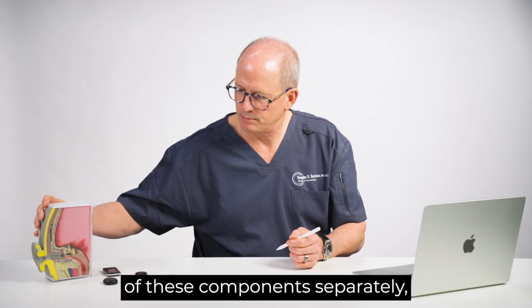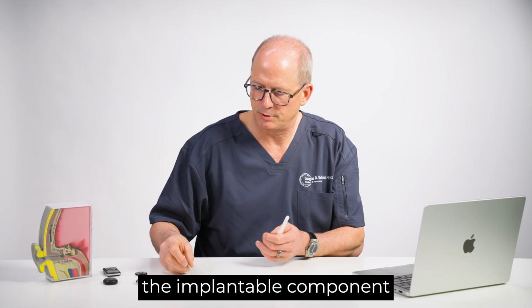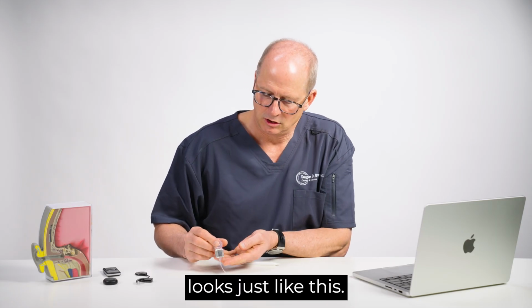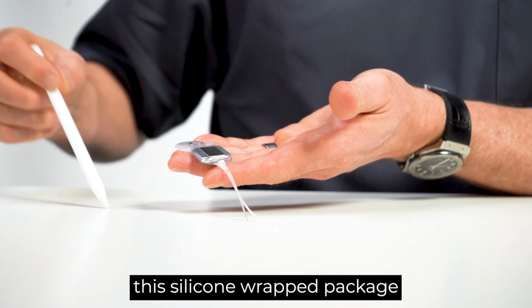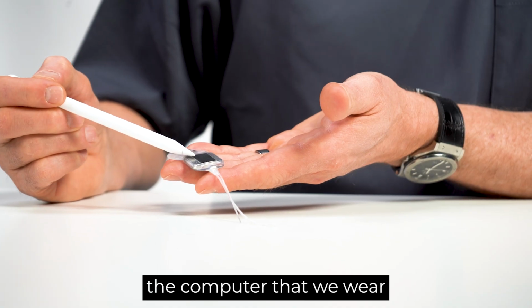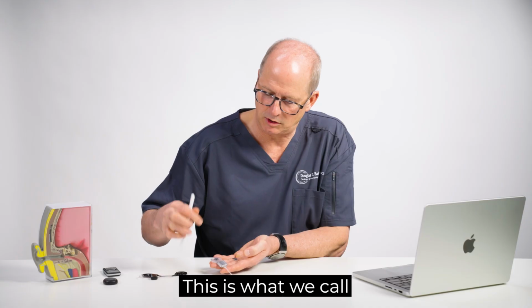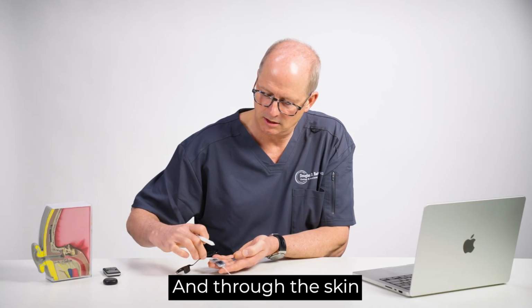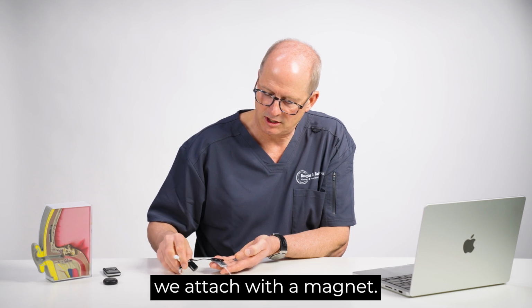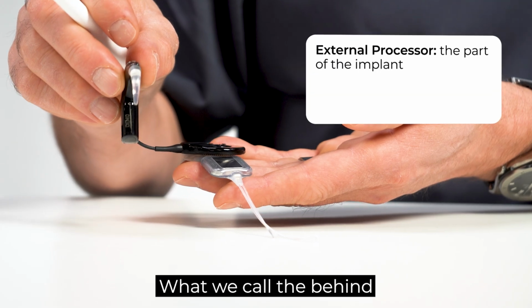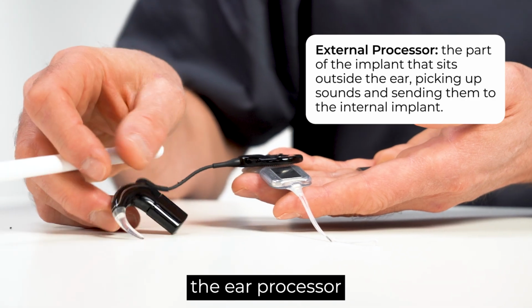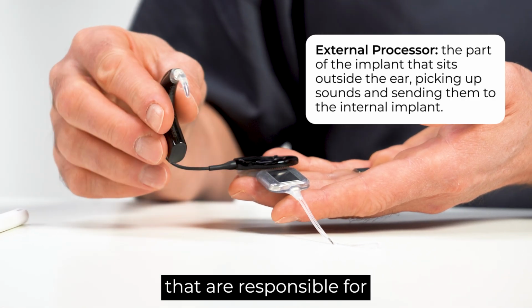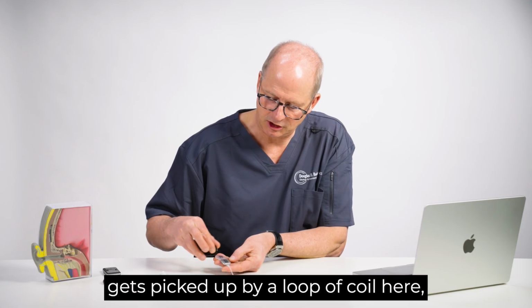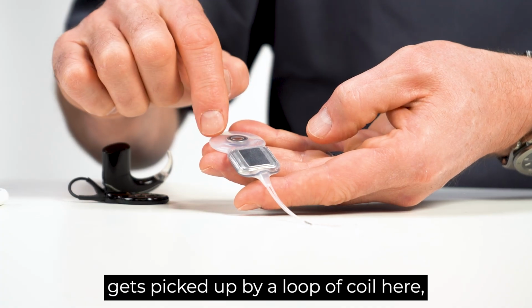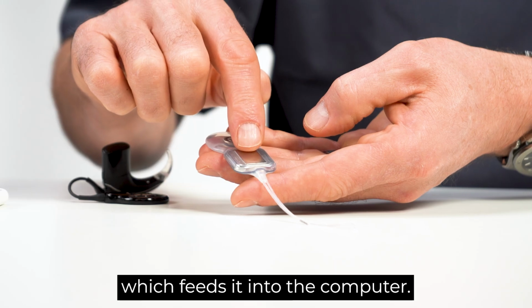So if we look at each of these components separately, the implantable component looks just like this. So you have a silicone wrapped package where this is the computer that we wear underneath the skin. This is what we call the receiver stimulator. And through the skin, we attach with a magnet what we call the behind the ear processor, or the external components that are responsible for receiving the signal, crossing over the skin, gets picked up by a loop of coil here, an induction coil, which feeds it into the computer.